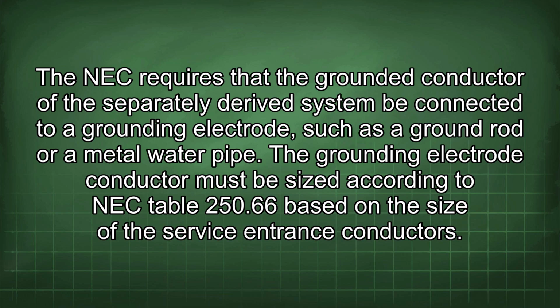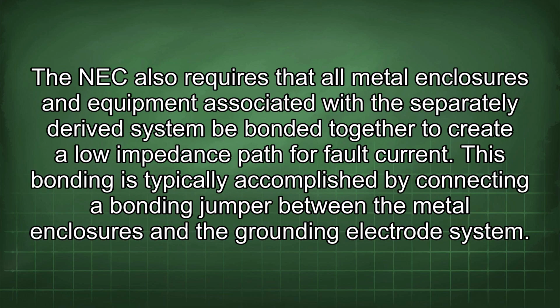The grounding electrode conductor must be sized according to NEC Table 250.66 based on the size of the service entrance conductors. The NEC also requires that all metal enclosures and equipment associated with the separately derived system be bonded together to create a low impedance path for fault current. This bonding is typically accomplished by connecting a bonding jumper between the metal enclosures and the grounding electrode system.